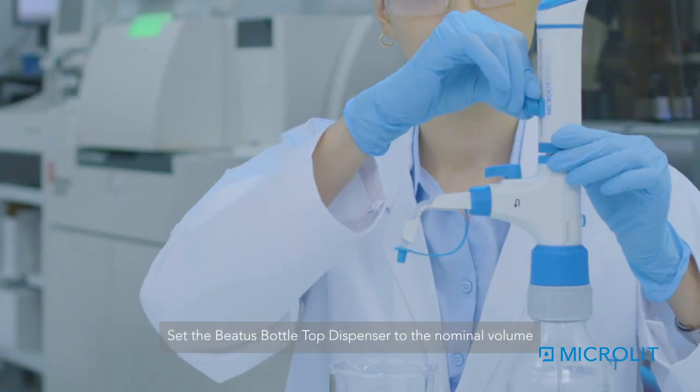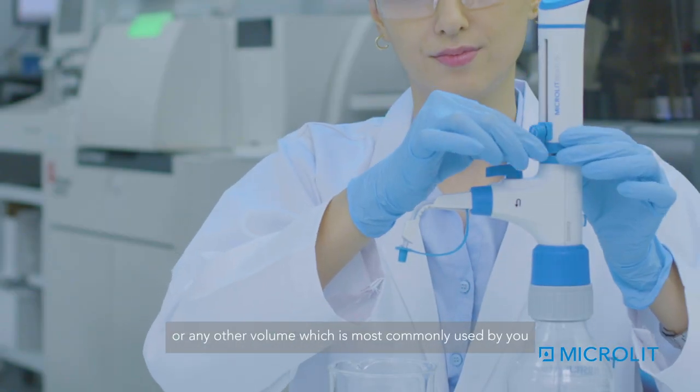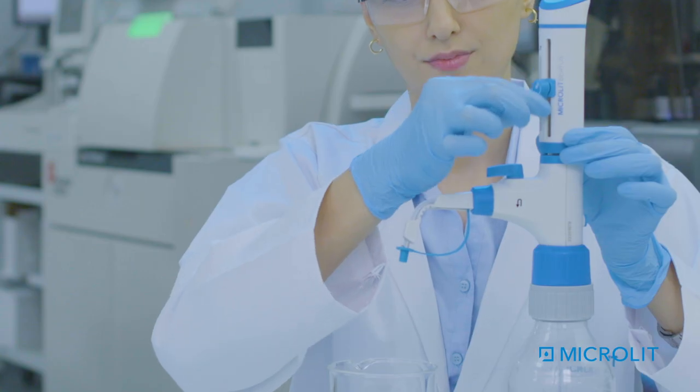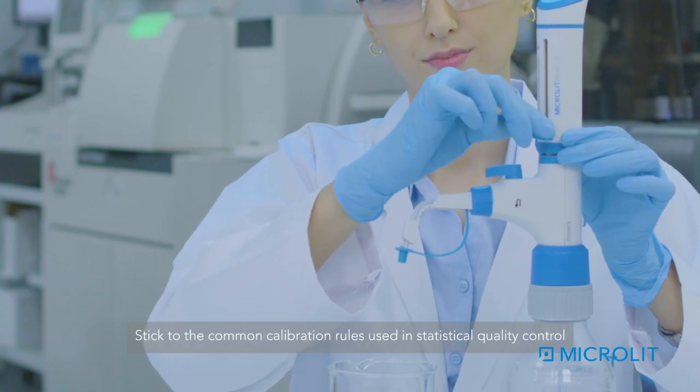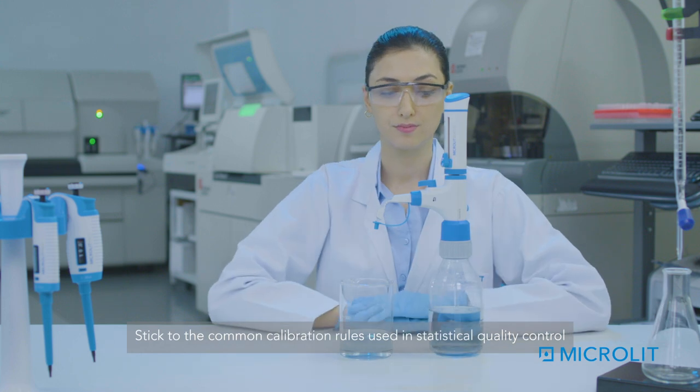Recalibration. Set the Beatus Bottle Top Dispenser to the nominal volume, or any other volume which is most commonly used by you. Stick to the common calibration rules used in statistical quality control.